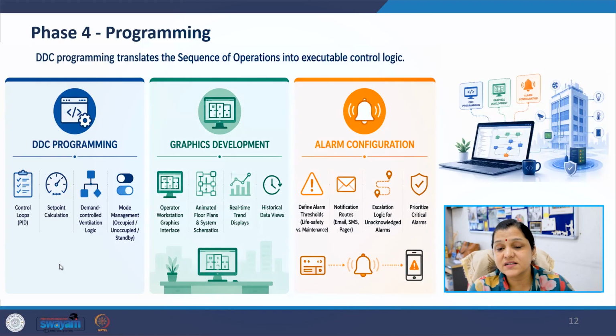Another critical task is alarm configuration. Not all alarms have the same priority. Life safety alarms must receive immediate attention. Maintenance alarms may follow lower priority levels. Notification routes and escalation procedures must also be defined carefully. A poorly programmed BAS creates operator confusion and unstable building performance.